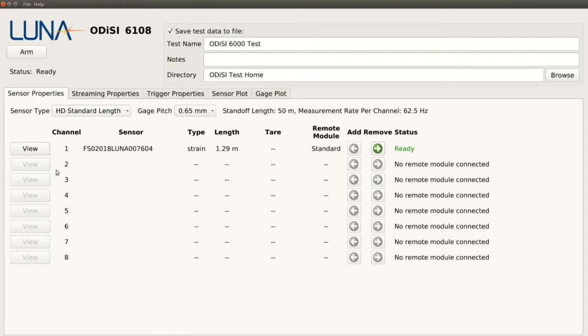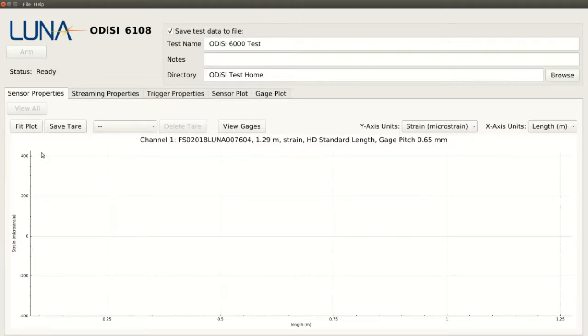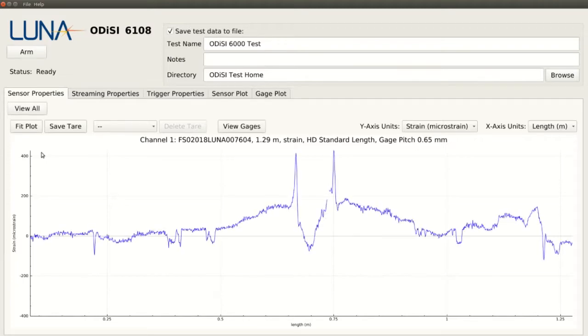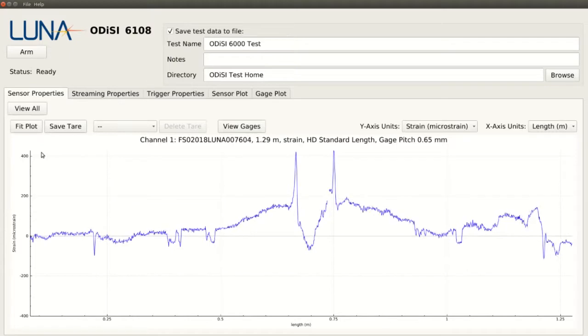If we click the View button next to our sensor, we can get a preview of what our data will look like. We'll usually find that there is already some strain imparted on our sensor. This is because the process of instrumenting a component imparts some strain on the sensor when compared to the unstrained reference that was saved in our key when it was manufactured.